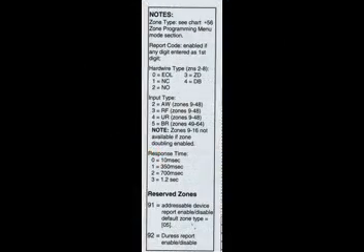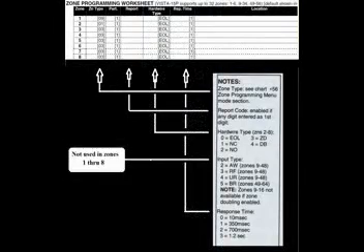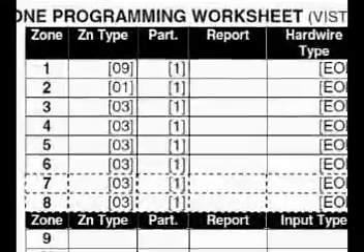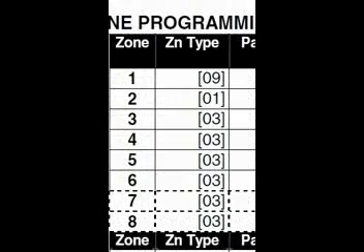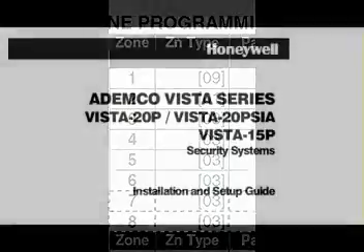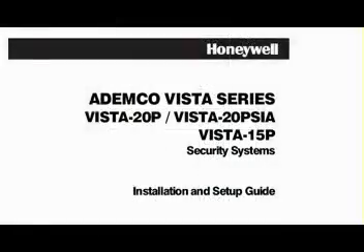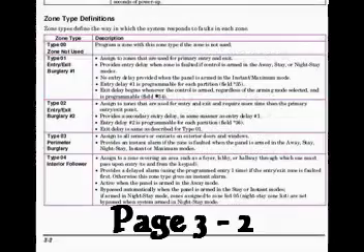On the left side of this worksheet you'll find a table showing acceptable values that can be used while programming, and here I've shown you how the table relates to the columns. Notice that for the first eight zones, you do not use input type — input type is used in expansion modules and RF zones. Moving in for a closer look, the first thing you're going to program will be zone type. Zone 1 is pre-programmed to zone type 9. The installation and setup guide on page 3-2 has many pages of zone types with a detailed analysis of what each can and can't do.